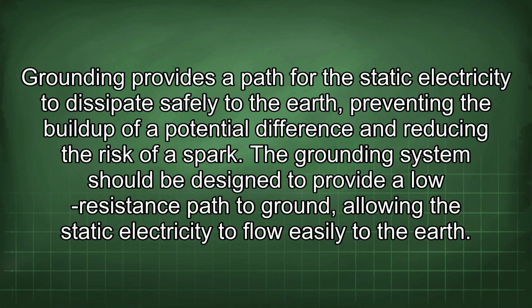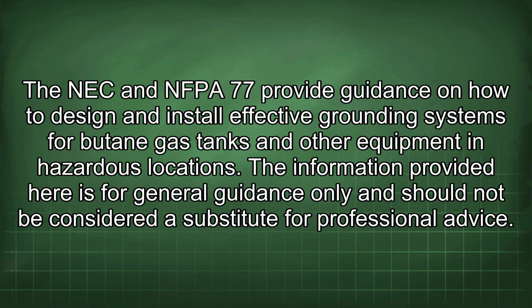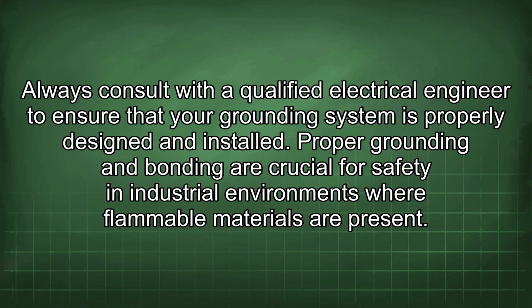The grounding system should be designed to provide a low resistance path to ground, allowing the static electricity to flow easily to the earth. The NEC and NFPA 77 provide guidance on how to design and install effective grounding systems for butane gas tanks and other equipment in hazardous locations. The information provided here is for general guidance only and should not be considered a substitute for professional advice. Always consult with a qualified electrical engineer to ensure that your grounding system is properly designed and installed.